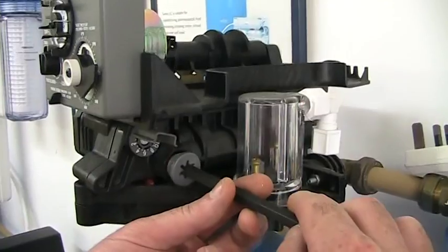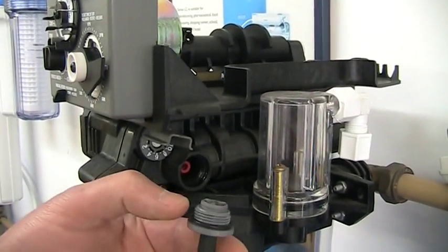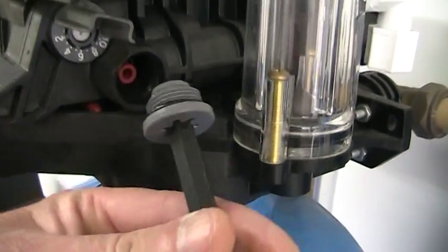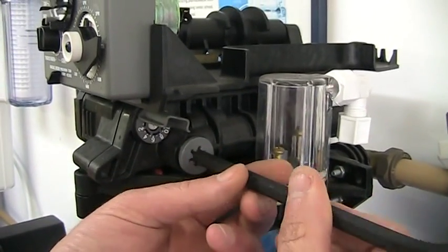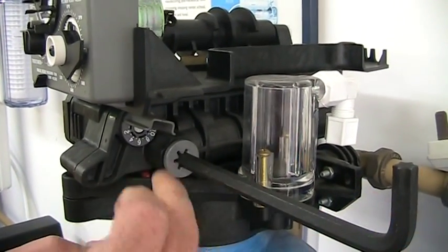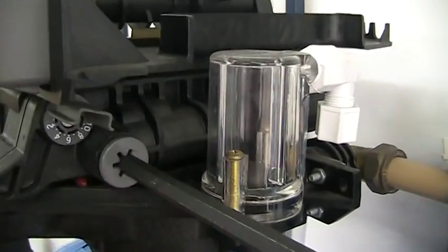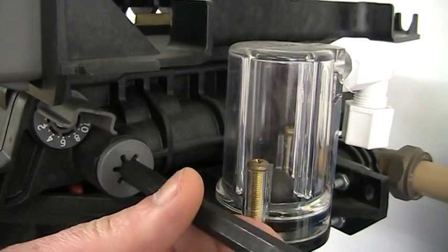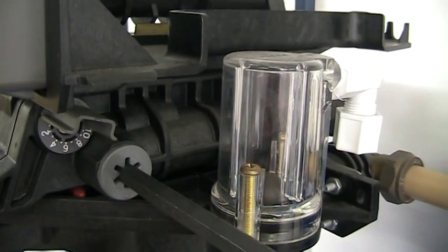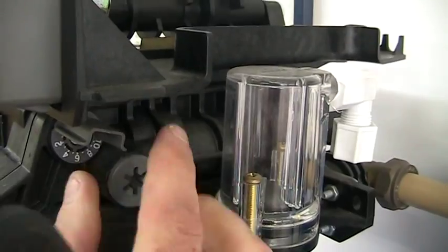You put back on your cap. Now you don't have to over-squeeze it, because there's an o-ring here, it does the sealing. To over-tighten it, because you have leverage with the allen key, will crack the top of it here, or the face of it here. So close it up. Nice squeeze. So that's the injector and the cap done on this side. We'll go to the other side now.